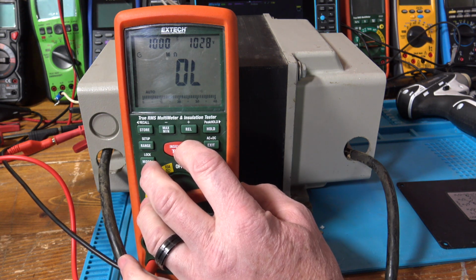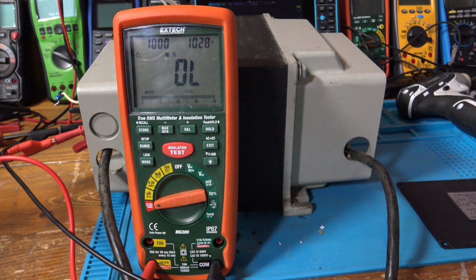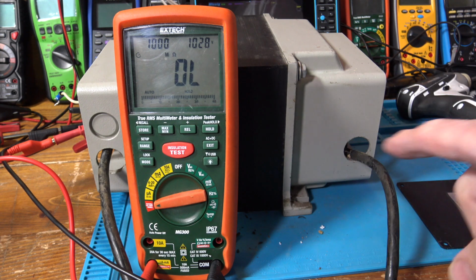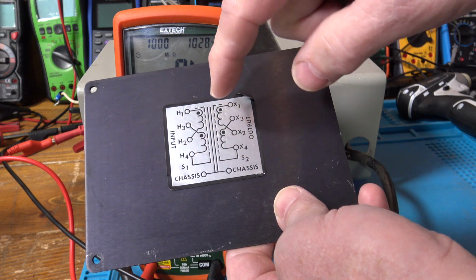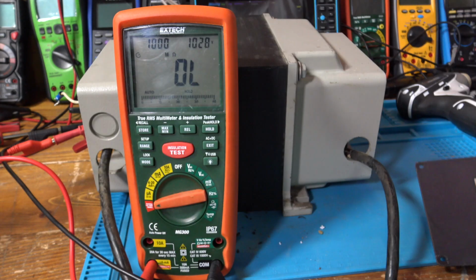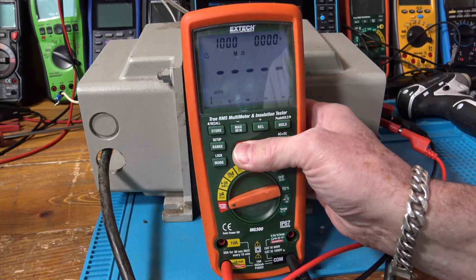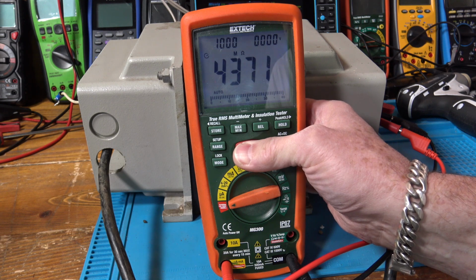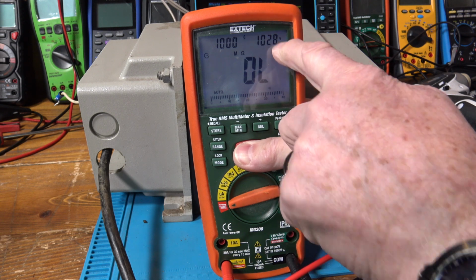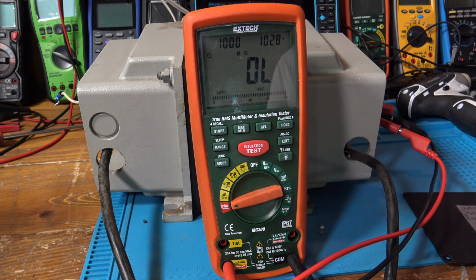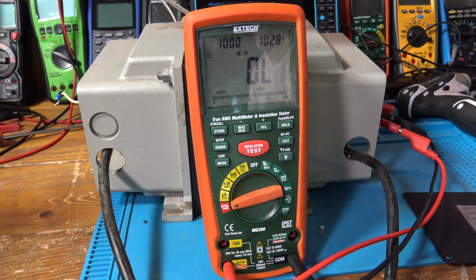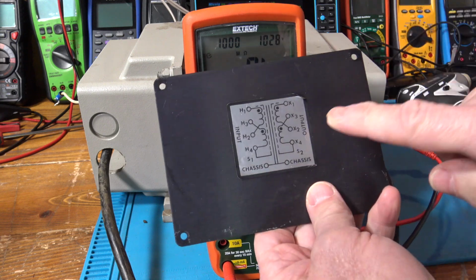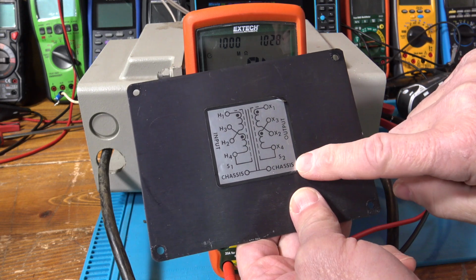One more time. So we got 1,028 volts there, test voltage. That looks good. Let's go back to this other side and just verify H3 and H1, H2 is isolated from H3, H4. Here we go. 1,028 volts, and it's open. All right, that's great. It looks like all four windings are isolated from chassis now, and all four windings are isolated from each other.